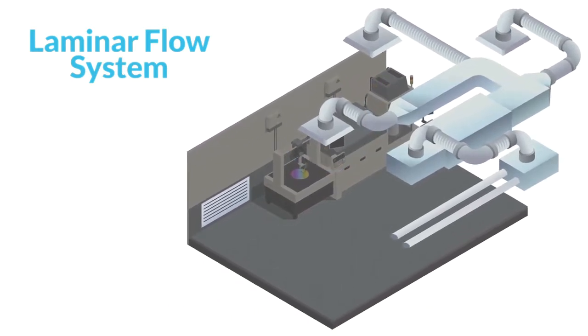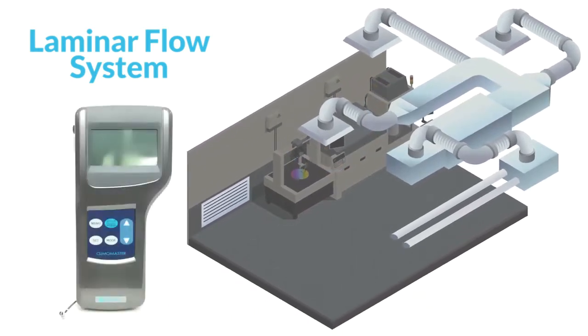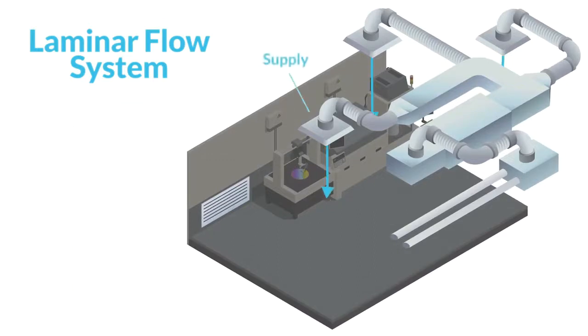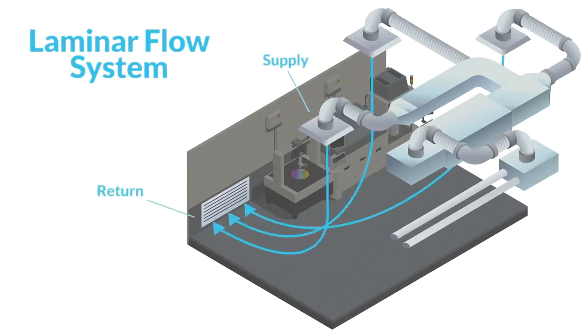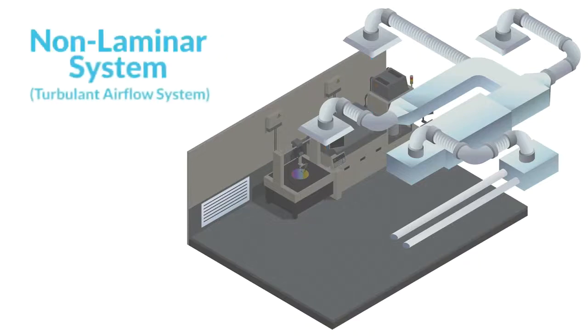Thankfully, modern anemometers like the Kanomax Climomaster come with the functionality to do the calculating for you. When working with a laminar flow system, always check that the flow of the air throughout the room is in fact flowing in a laminar fashion and flows at the speed specified in the design specifications for the room. The second common type of ventilation system is non-laminar or turbulent airflow.